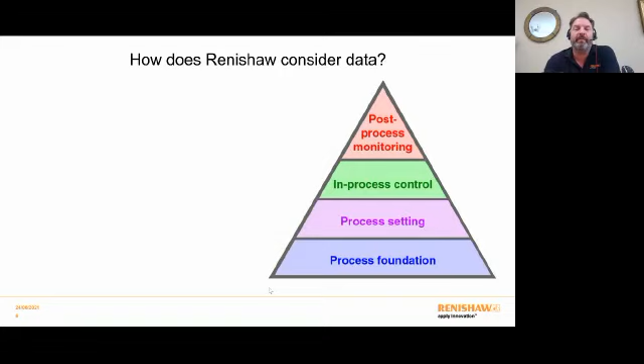Calibration is very important. Being able to understand periodically whether the equipment that I'm using is capable of doing the job that I expect it to do, and being able to proactively take out some calibration or health data from that device, is very important. You then focus on, okay, I've got a machine that I know can produce what it's doing, but somewhere there has to be a process that's actually going to make the thing that I'm making, and I need to implement some checks within that so that I've set the process up correctly, and I am also periodically checking that that process is doing what it's supposed to be doing.